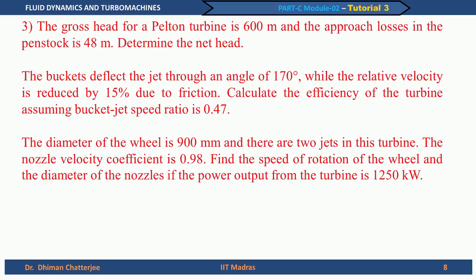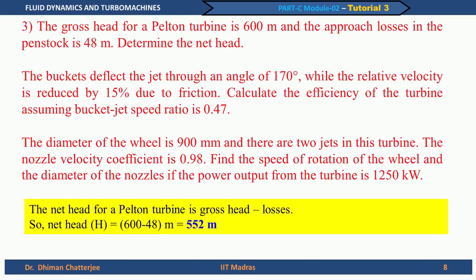The gross head for the Pelton turbine is 600 meters and the approach losses in the penstock are 48 meters. The net head available to the turbine is gross head minus approach losses, giving a net head of 552 meters. The buckets deflect the jet through an angle of 170 degrees while relative velocity is reduced by 15 percent due to friction. We need to calculate the efficiency assuming a bucket-to-jet speed ratio of 0.47. The wheel diameter is 900 mm, there are two jets, and the nozzle velocity coefficient is 0.98. We also need to find the rotational speed and nozzle diameter for a power output of 1250 kW.